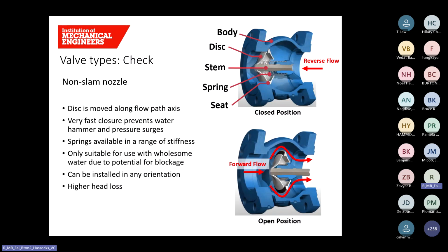A non-slam nozzle check valve is a spring-assisted axial flow check valve. So when fluid flows forward, the disc opens smoothly. As flow slows or reverses, the spring quickly pushes the disc shut. This minimises the slam that causes water hammer. The springs themselves are available in a range of stiffness, and this enables the valve's dynamic closure characteristics to be matched to the system requirements. As you've probably already noted, this valve is only suitable for use with wholesome water, and that's due to the potential for blockage. These valves can be installed in any orientation. These valve types usually incur a higher head loss when compared to other check valves.